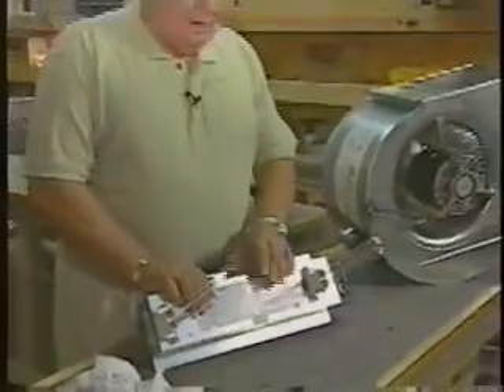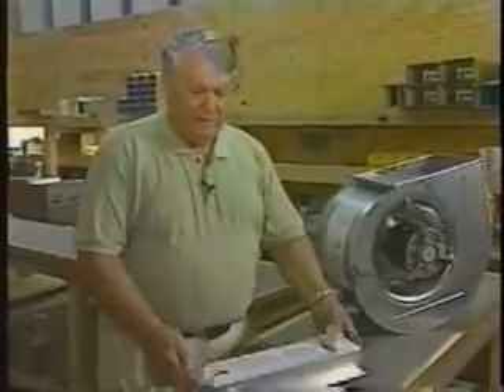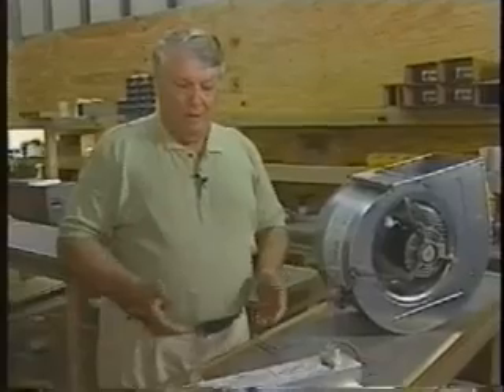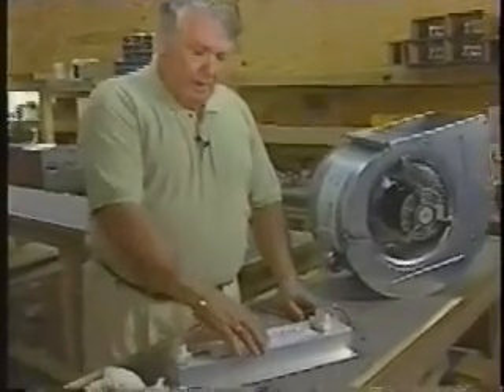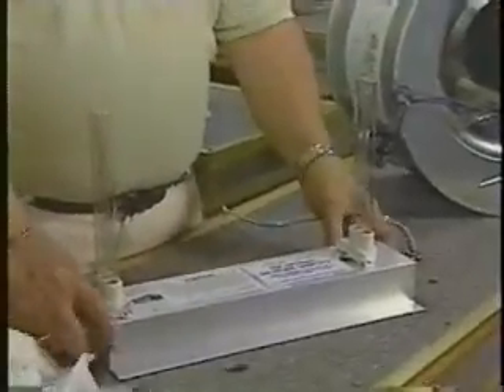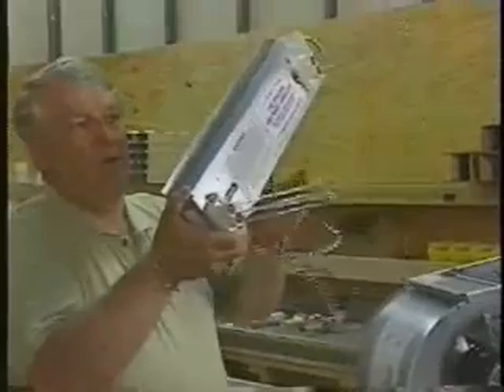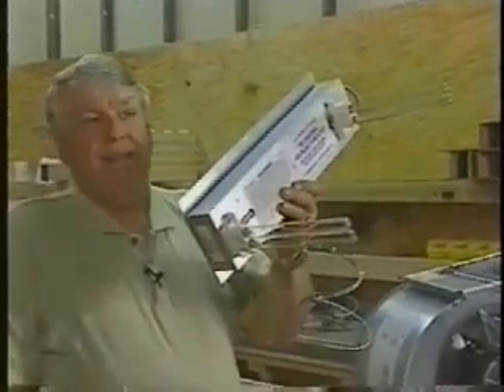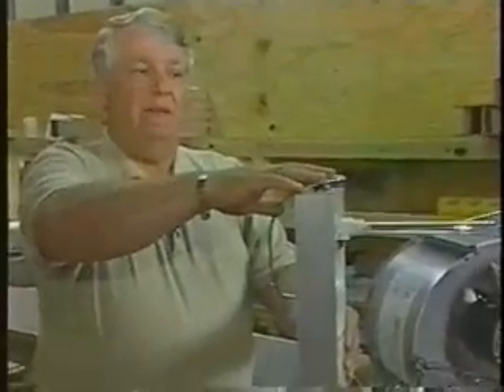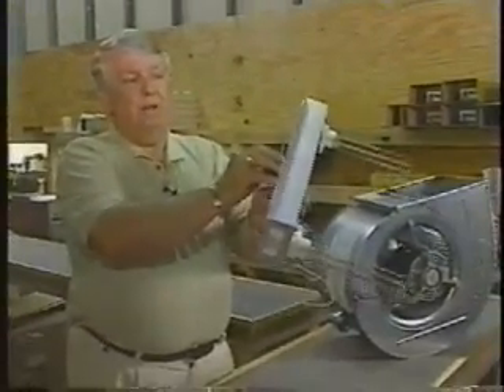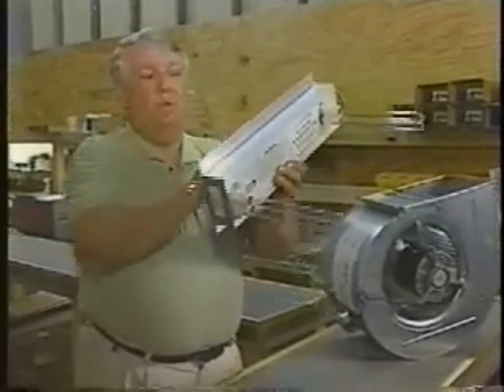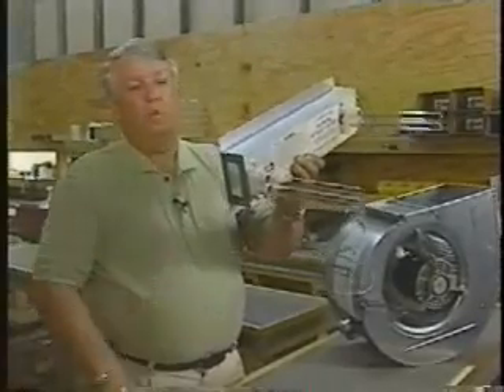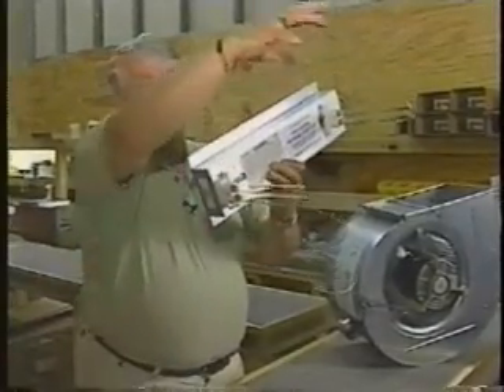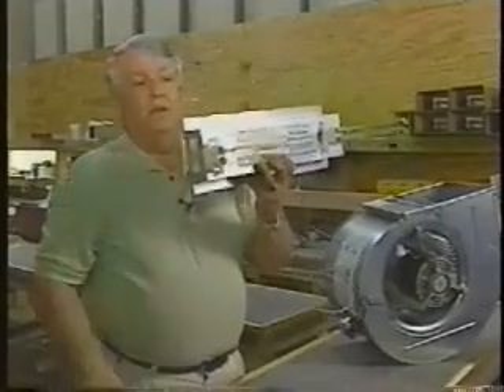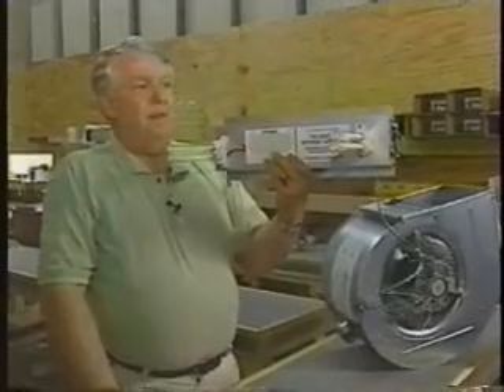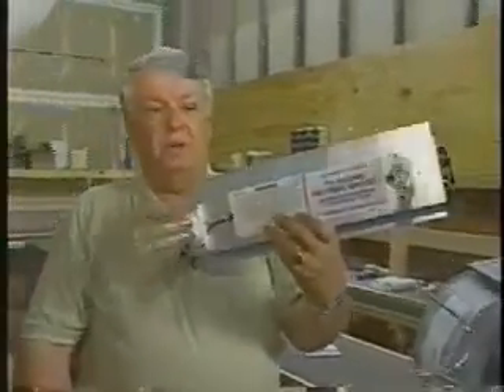There are some cases with your A-frame units where your A-frame is in the top instead of the bottom. In a case like that, you have to cut a hole 4 inches by 17 inches and insert this into the ductwork. When you insert it, you'll ask for a T-model, which has all the controls on top of the unit instead of on the end, so when you push it in, the controls won't be in the way. Just strap it in with aluminum duct tape. You do want these to shine down on the bottom, on both sides of your A coil. There are very few installations like that, but this unit is adaptable and can be used in that particular instance.